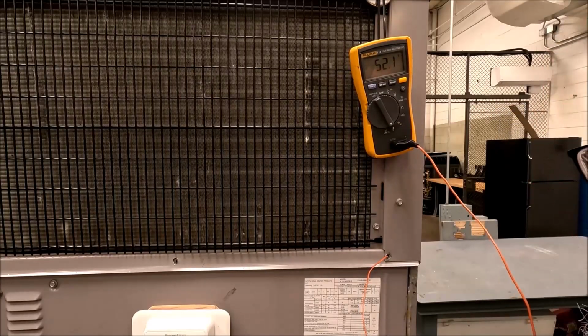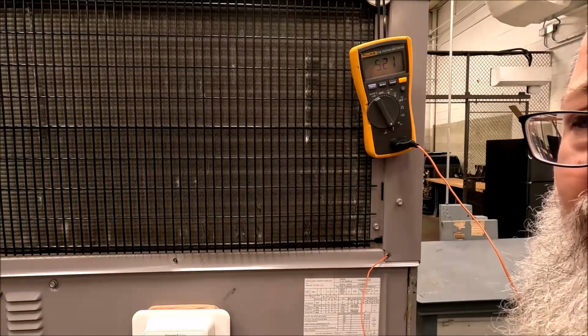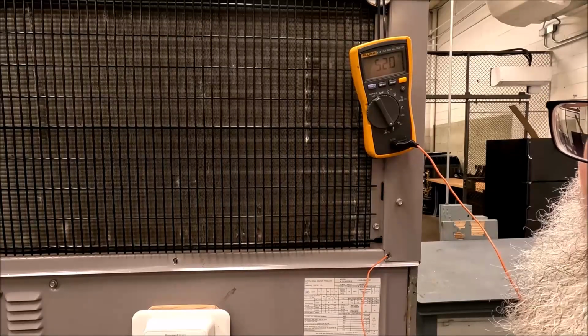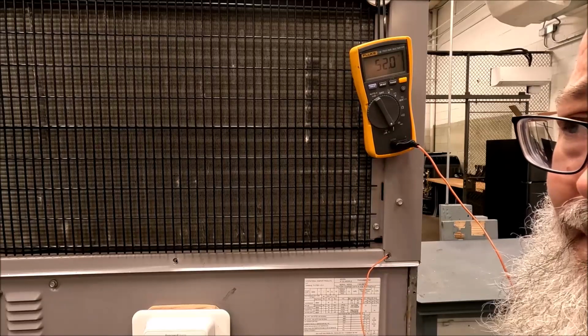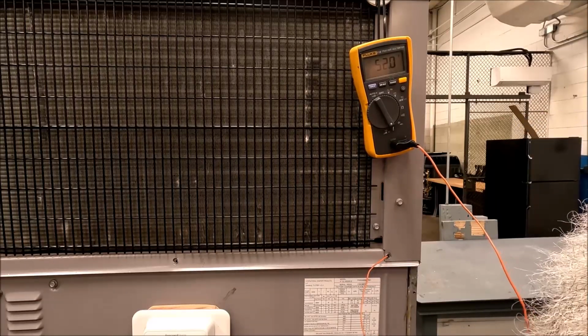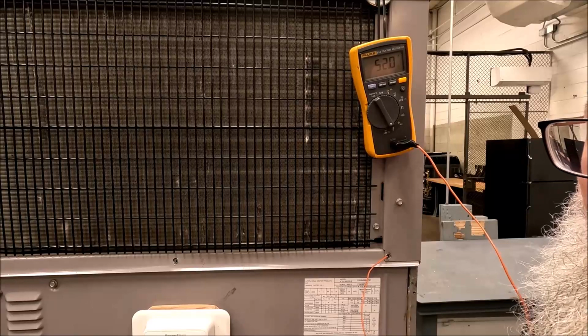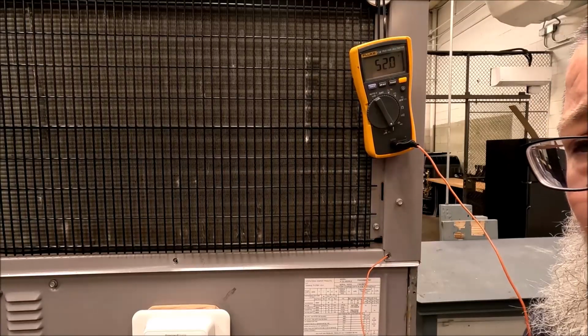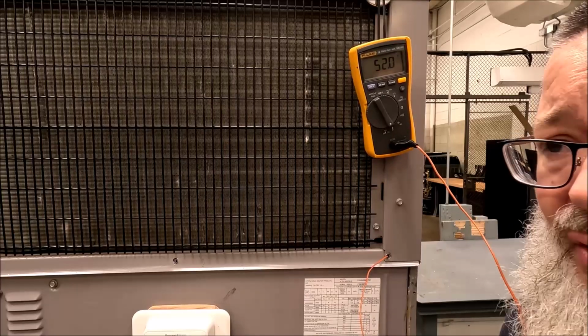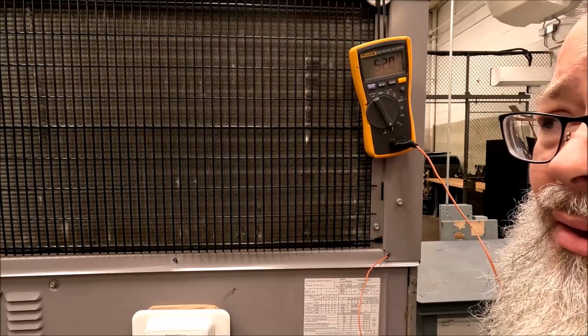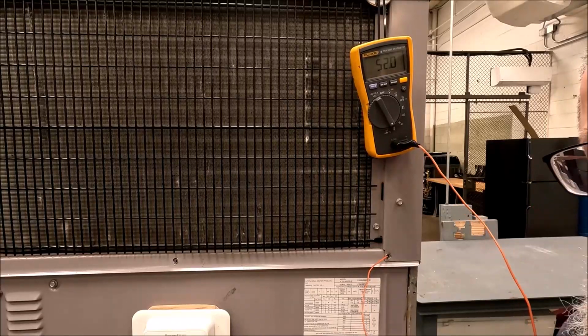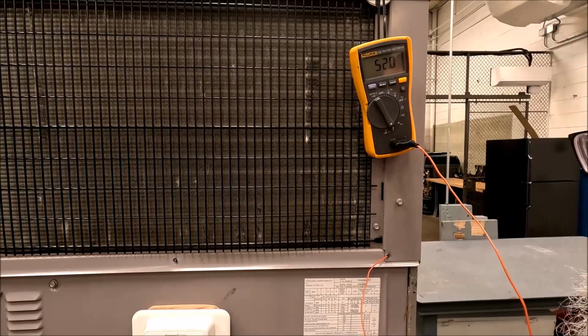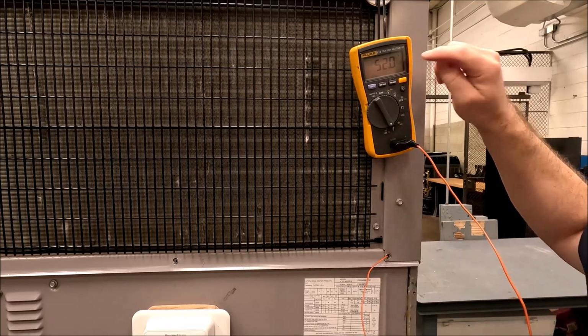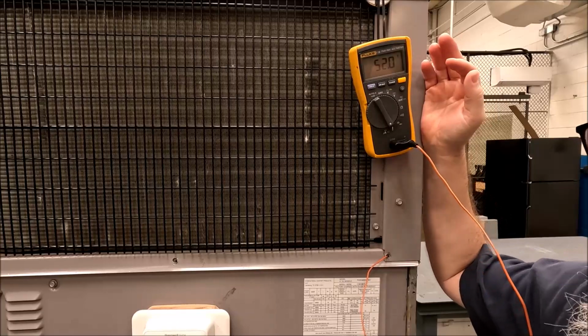So it just happens to work out in our case that the low side pressure connection was where the vapor line, where we needed to be. And on a package unit, that heat pump over there, no matter if we're in heat or cool mode, the reason they give you those 2 ports and only 2 ports is it's always high and it's always low. So hope this helps a little bit. Gets me back in the shop and doing some things. But yeah, 52 degrees, 71 going in, 19 degree split. We're all right today.